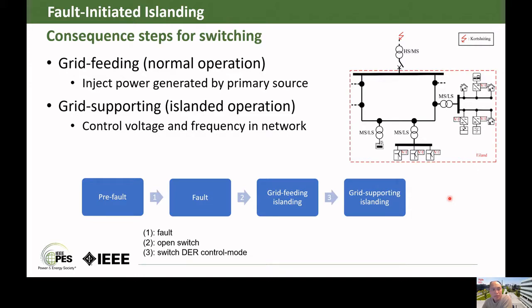When the fault occurs, the sequence is as follows: first, with the fault occurring, we switch from pre-fault to fault conditions. Then there will be switch opening, and the grid feeding islanding mode kicks in. Then we have to switch the operation mode of the DER to grid supporting islanding.